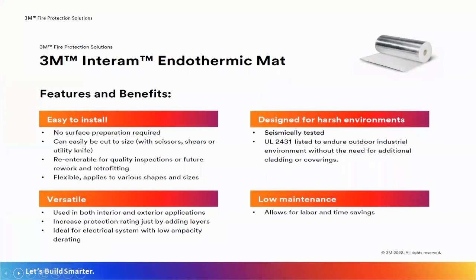Next slide, please. So some of the advantages of the EMAT, as I had mentioned, it's relatively easy to install. There's no surface preparation required. So whatever the item is you're wrapping, you don't have to worry about cleaning it off first because you're not relying on an adhesive bond. Basically, it gets wrapped around that item and secured with stainless steel banding, which also makes it easy to re-enter for quality inspection or if there's future rework. Since it's a flexible wrap material, it will conform to various shapes, and it can be used in both interior and exterior applications. Next slide, please.